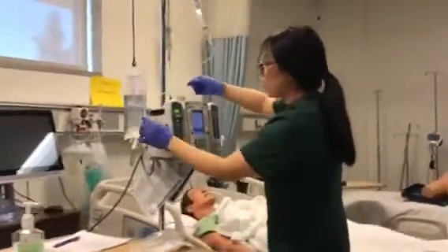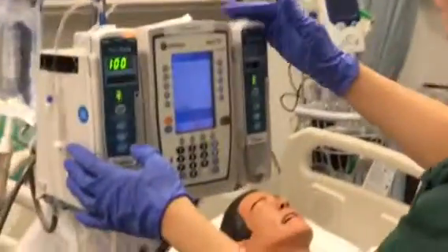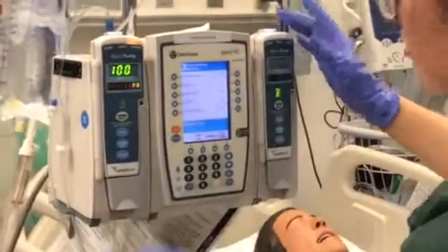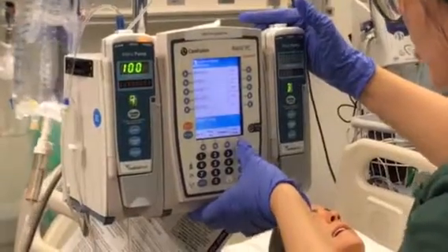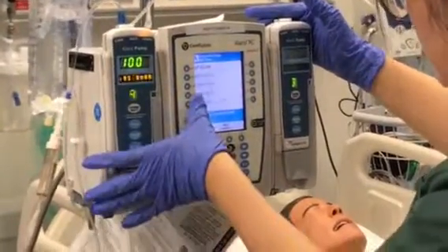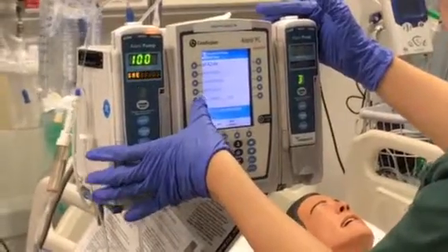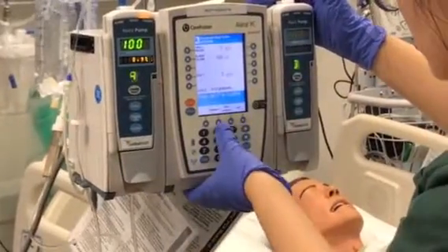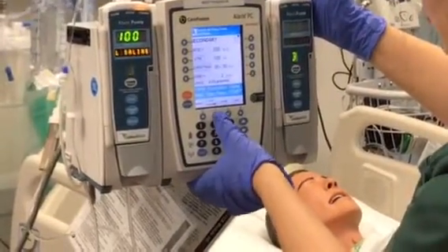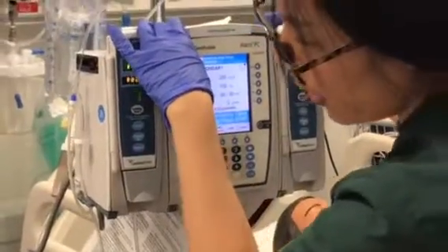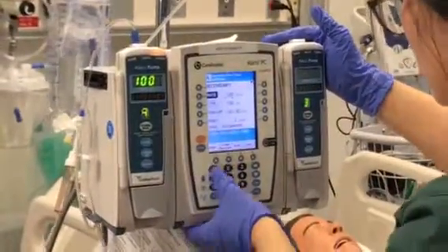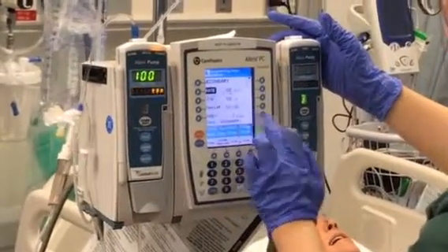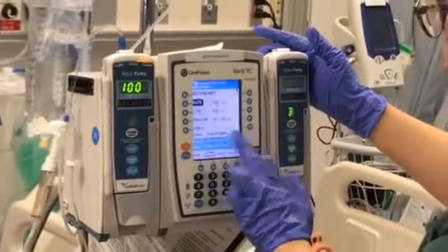After all these, I'm going to program the secondary bag. Go to channel selection first, then secondary, then choose the medication, which is cefazolin. Then the medication is 2 grams in 100 ml. So confirm here, go to the next, set up the rate and volume here. The rate is 100 milliliters in 1 hour. So in this case, this medication will run about 1 hour and the dosage is 2 grams.